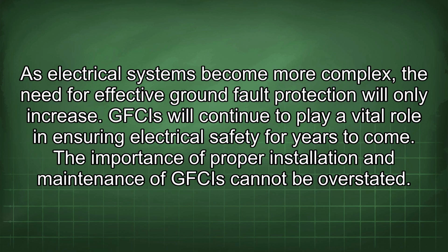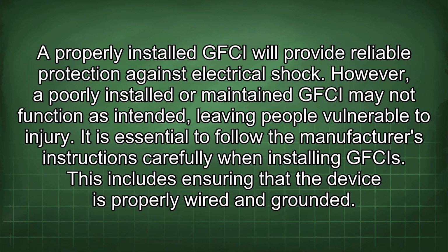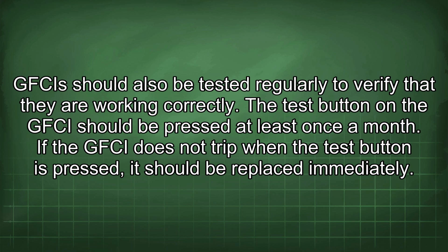The importance of proper installation and maintenance of GFCIs cannot be overstated. A properly installed GFCI will provide reliable protection against electrical shock. However, a poorly installed or maintained GFCI may not function as intended, leaving people vulnerable to injury. It is essential to follow the manufacturer's instructions carefully when installing GFCIs. This includes ensuring that the device is properly wired and grounded. GFCIs should also be tested regularly to verify that they are working correctly. The test button on the GFCI should be pressed at least once a month. If the GFCI does not trip when the test button is pressed, it should be replaced immediately.